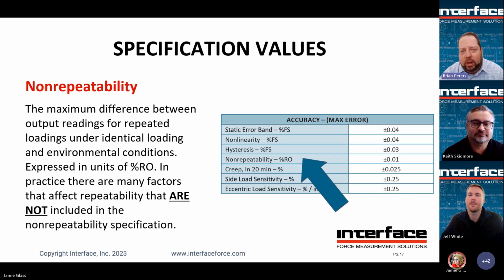So non-repeatability. Non-repeatability is essentially, as it says, how often or how much a sensor will deviate if you test it over and over again. Now, the key to note here is that's in identical loading and environmental conditions. So everything is being held constant. Typically, it would even be in the same installation. So you can imagine in the real world, you can't take this specification and assume that the sensor is going to be repeatable from test to test based on this specification.